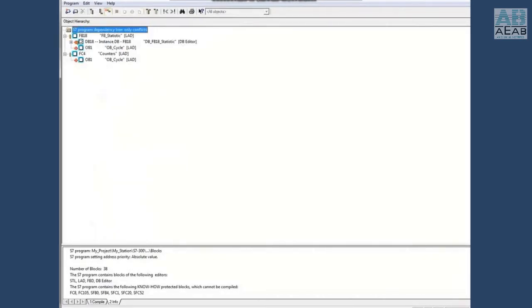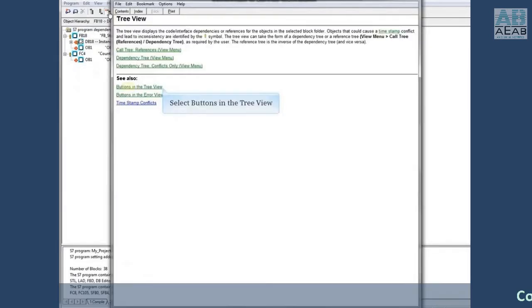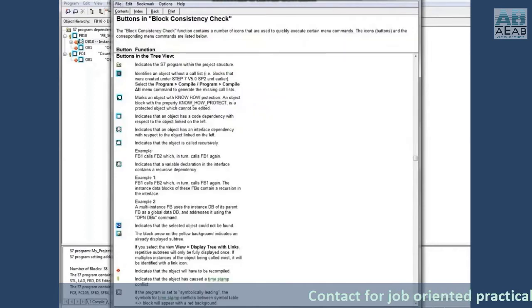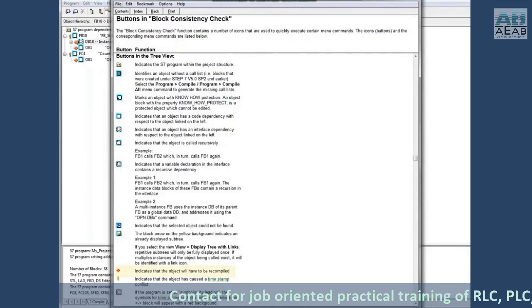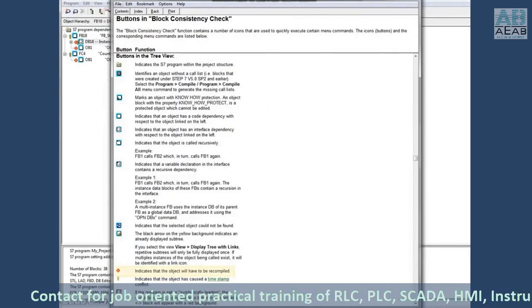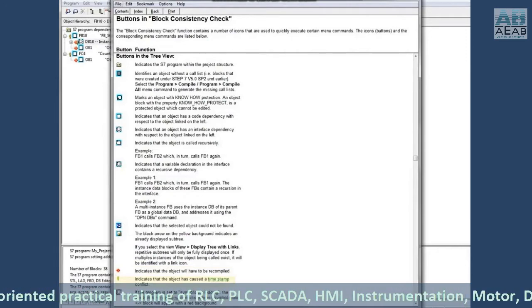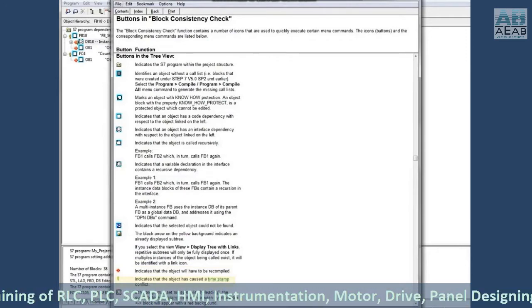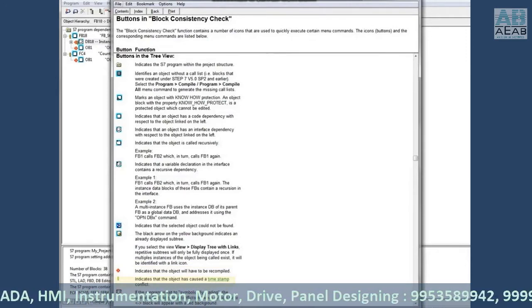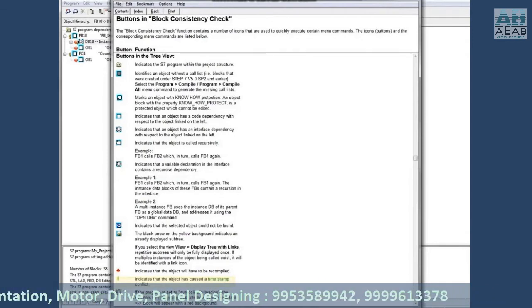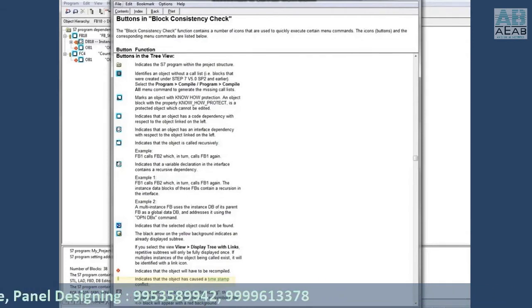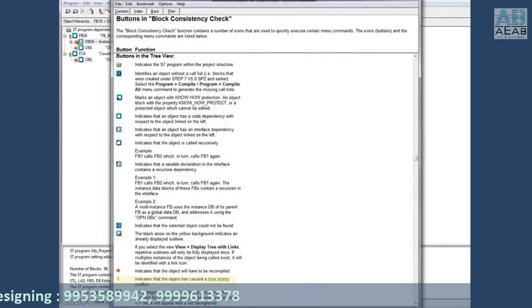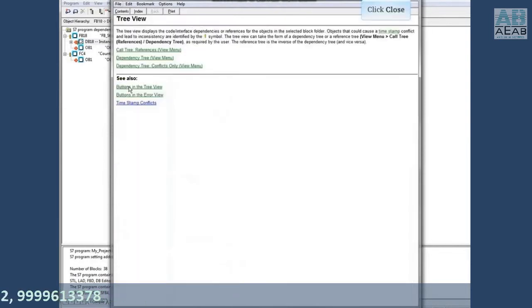This shows only the blocks that have interface problems. To see the meaning of the icons, press F1 for help and click buttons in the tree view. The red X indicates that the object must be recompiled and the yellow exclamation point indicates the timestamp conflict, which generally means that there is an interface problem such as added local variables to the block where the call to the block is not updated. Close the help screen.